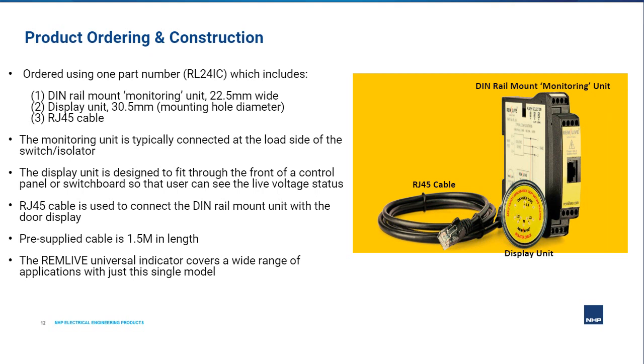The display unit includes LEDs to indicate the live voltage status and is designed to fit through the front of a control panel or switchboard so that the operator can clearly view the voltage presence status. And then finally, the RJ45 cable, which is used to connect the monitoring unit with the display. The cable is pre-supplied in a 1.5 meter length size. The REMLIVE universal indicator covers a wide range of applications with just this single model or part. We'll look into its features in more depth to appreciate this point more.